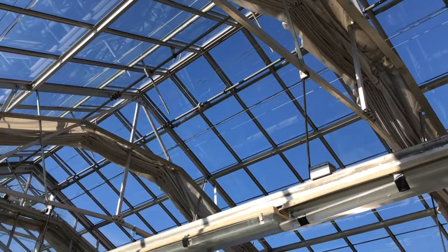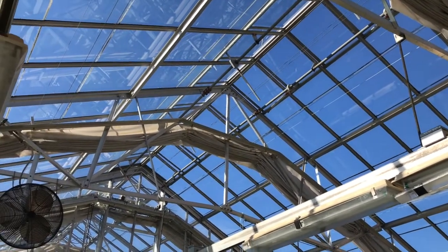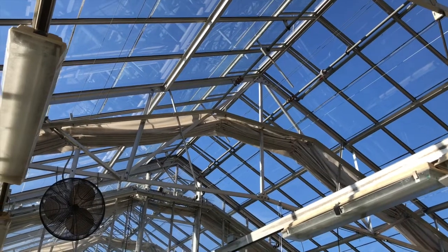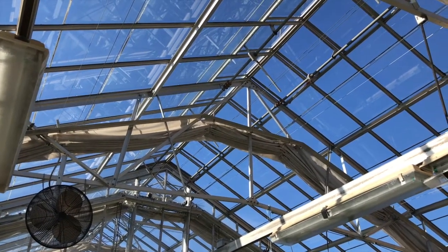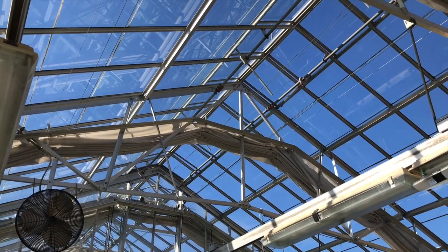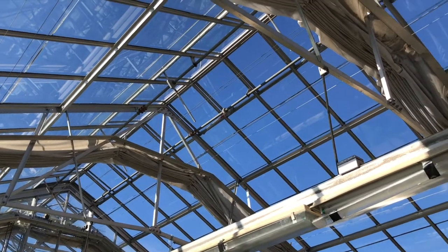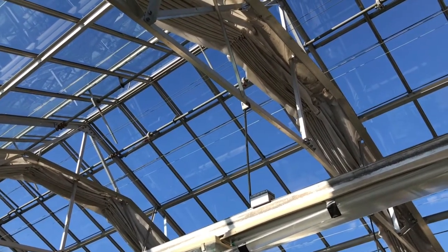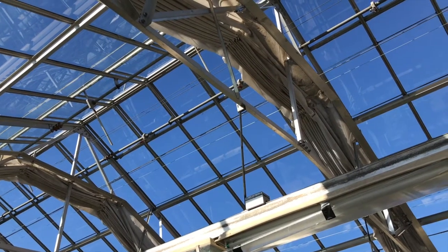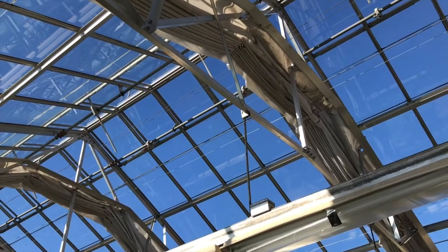One of the first stages of cooling in the greenhouse is for just the vents to open up. So if those center roof vents open up, it allows for cool or cold air to come into the greenhouses. And then after that stage, those vents will close, and then the fans will come on the wall, and we'll draw air through the pads to cool the greenhouses. But initially, the cooling begins in the ceiling.